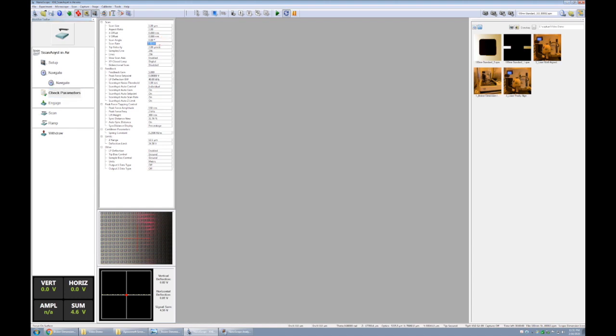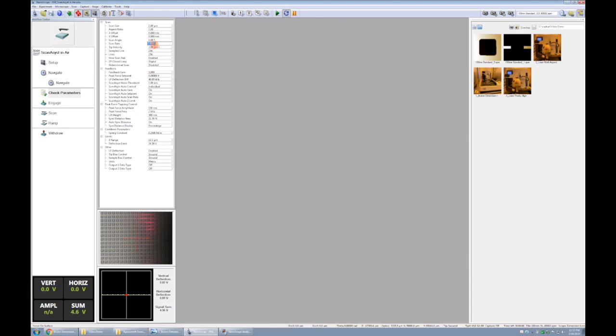The scan rate is the number of lines scanned per second. Right now at one hertz, we're going to scan one line per second. Each scan line includes both the forward direction and the reverse direction, or as we call it on the software, the trace and the retrace. Right now, if we have a one micron field of view, we go one micron in the trace plus one micron in the retrace once every second. So we travel two microns every one second, or in other words, we go two microns per second.